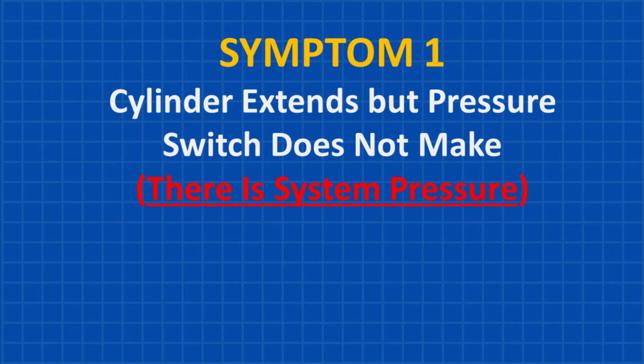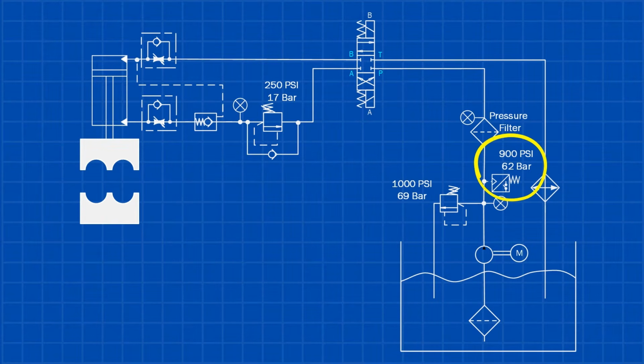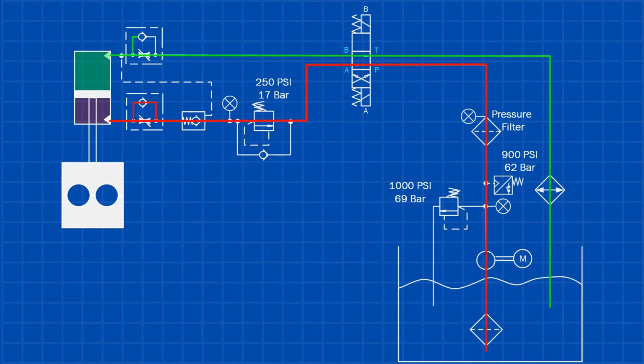Symptom 1. Pressure switch does not activate at the set pressure. Certain hydraulic systems, such as foundry molding machines and hydraulic presses, rely on reaching a specific pressure to complete their cycle. A pressure switch ensures this process happens correctly. If the switch fails to activate, the cycle times out, causing the cylinder to retract before the process is complete. Run the cycle once and monitor the pressure gauge to see if it reaches the set pressure. If the gauge shows the correct pressure but the switch doesn't activate, replace the pressure switch.